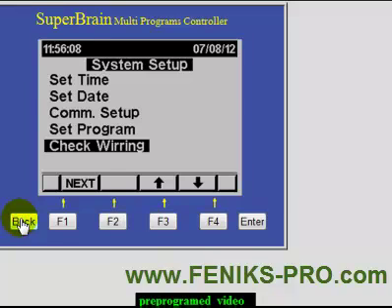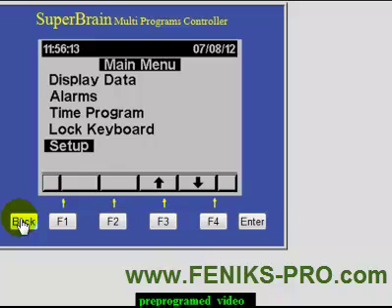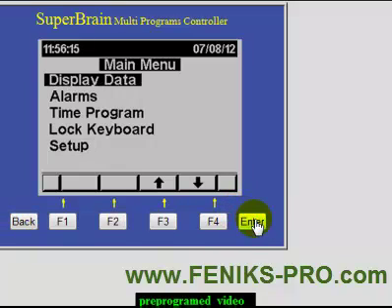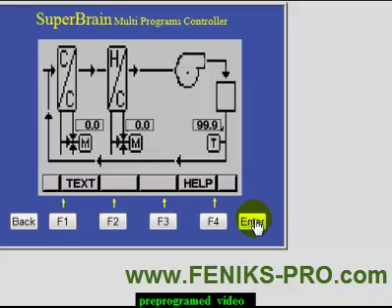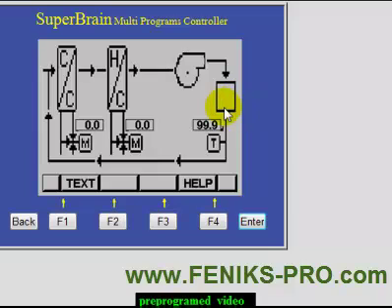Let's go back and display the data. Here you have it — here is the picture, and this one is in black and white. If you want, you can change it to a color picture. Here you have a heating coil, here a cold water coil, and this is the fan — it sucks air inside. If one is on, it's for cooling the room. If the other one is on, the first one is off, and it's for raising the temperature in the room. And this is the temperature sensor.